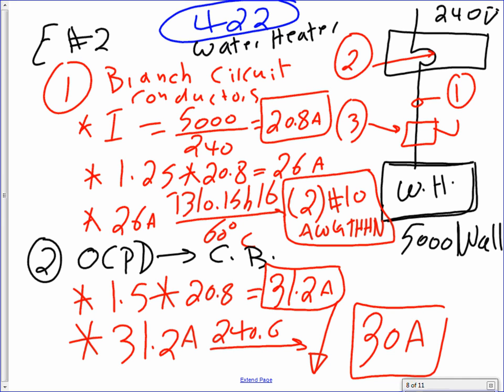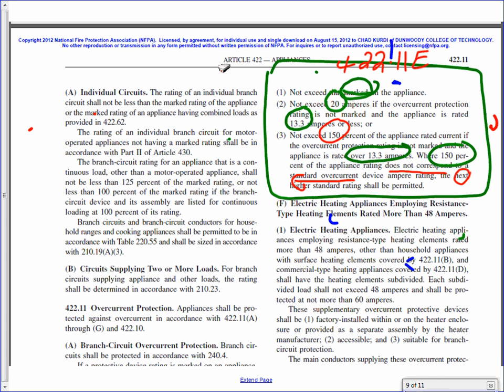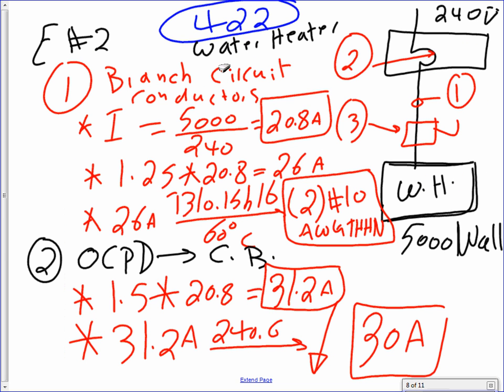So here's my overcurrent protection device. The 1.5 is right here: not exceeding 150% of the appliance's rated current if the overcurrent protection device is not marked and the appliance is rated over 13.3 amps. That's where the 1.5 came from. Can you see that? Okay, so even though you can go up, I went down. Down is safer.